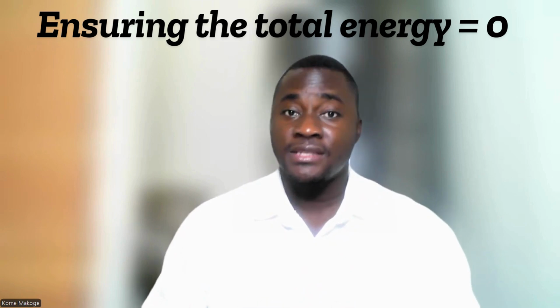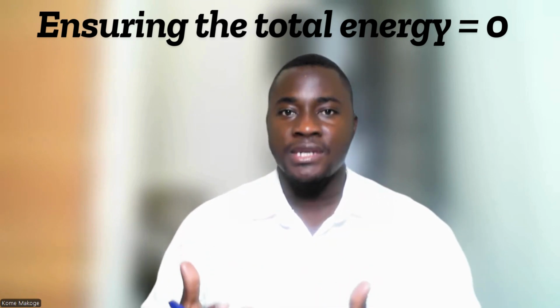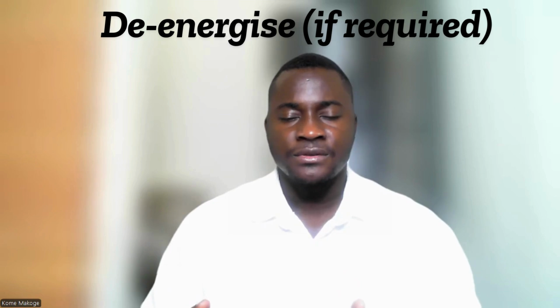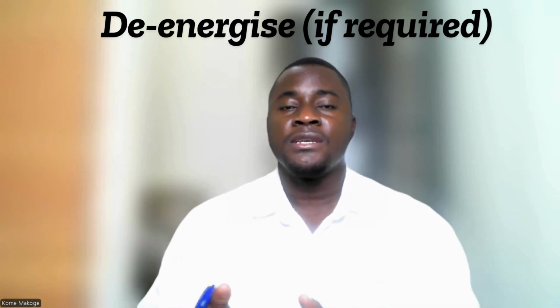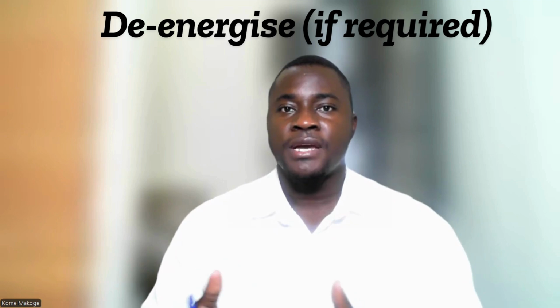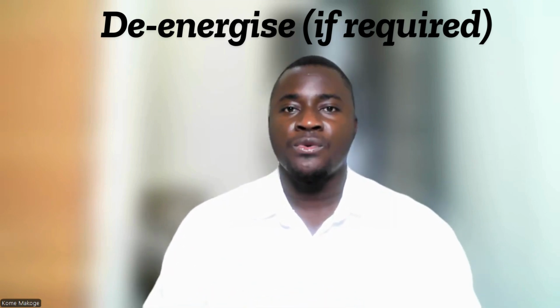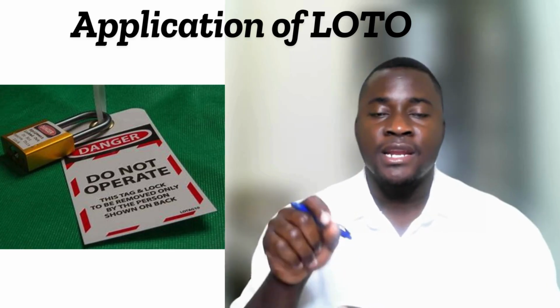So when you shut down the system, the next point now will be checking if the total energy of that system is equal to 0, which is the original intent of isolation. So now when you check, of course, you might still have some kind of residual energy. As such, now we move over to de-energization. With de-energization now, to actually confirm that the total energy of the system will be equal to 0 is very important. Once you are done with confirming that, which is de-energization, and now you have the total energy of the system equal to 0, applying the lockout and tagout.